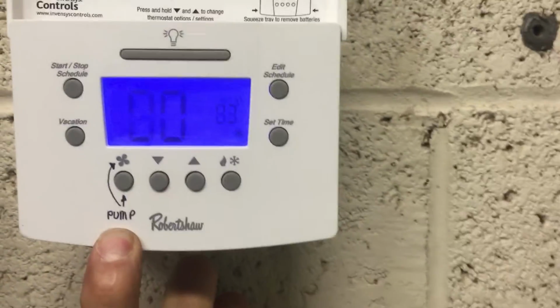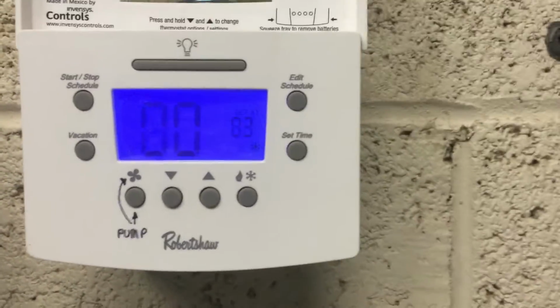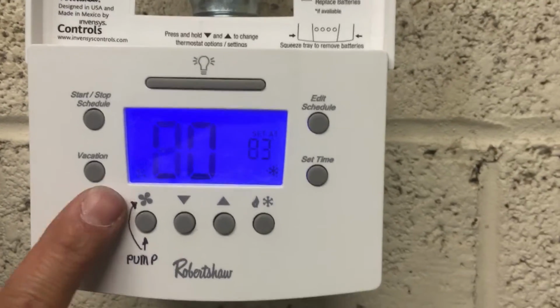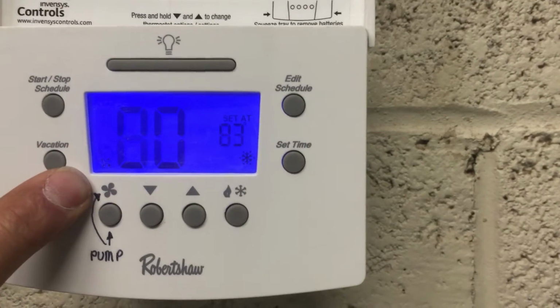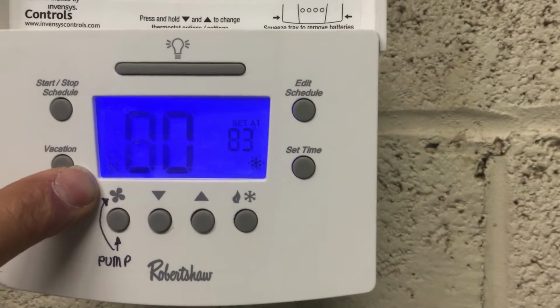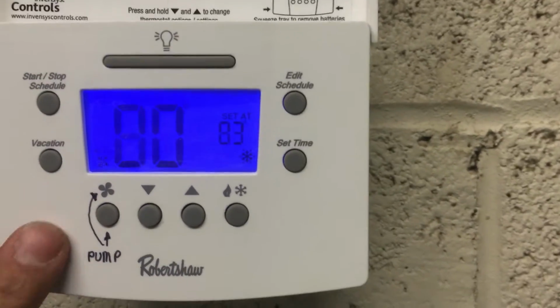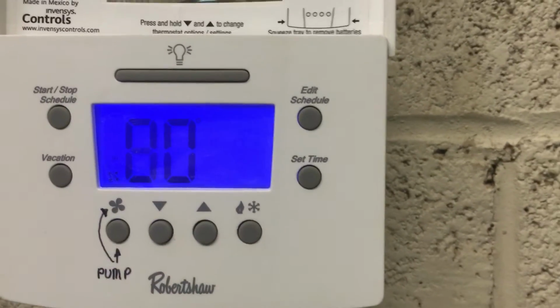The reason we do that is so we can pre-wet the pad before the first or second stage of cooling is called for. If you see, right now we have it in auto mode, the fan is not moving, but if it is on, this would be spinning, and it again is turning on the pump in our unit. In this application, the pump can be run in a couple different modes.